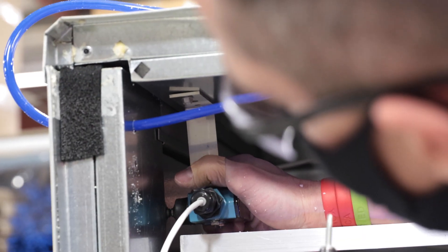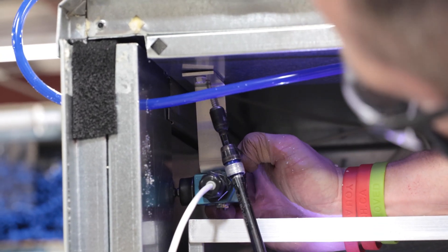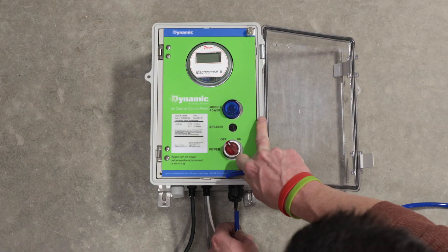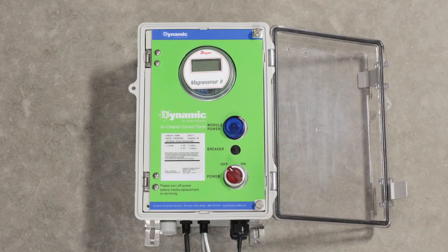Ensure that the provided access door interlock switch is installed in the air handling unit and operational. The air cleaners will not be energized if the door switch is not connected to the control panel. Attach the static pressure tubing to the control panel. Be sure to calibrate all Magnesense gauges to zero according to the gauge instructions provided.